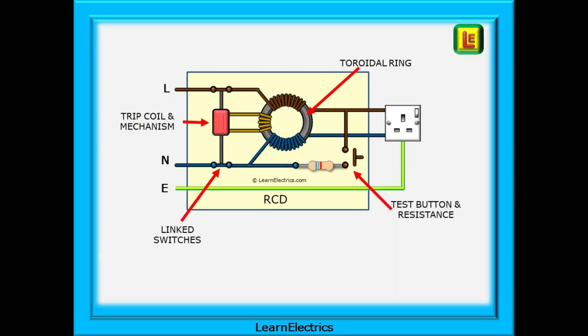These are the basic parts of a general purpose RCD. The input current flows along the line conductor and around a magnetic toroidal core, then to the points of use — a socket outlet in this case. The neutral currents that flow back also pass around the toroid, but wound the opposite way to the line. If input and output are the same, they cancel each other out with a net residual current of zero, and the RCD does nothing.